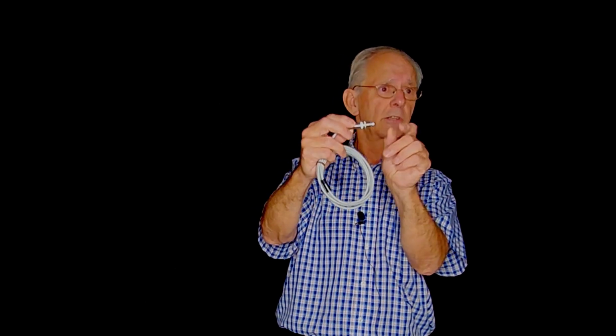This sensor is a limit switch, but the difference between this limit switch and the other limit switches I showed you is that this one can actually sense repeatably down to 2 microns. So this is used typically to set the home position for CNC machines and so forth. You move till you hit it, and you'll notice it has a lot of over travel. So you come in, you hit it, and then you back off and you wait for the switch to close. And the output's electronically switched, because the contacts in here, to prevent welding and damage to the contacts, use a very, very tiny current, which is then amplified on the output. And that's how they get the accuracy. It's not a snap action switch. Two pieces come together, and that's how it works. Used in CNCs and so forth.